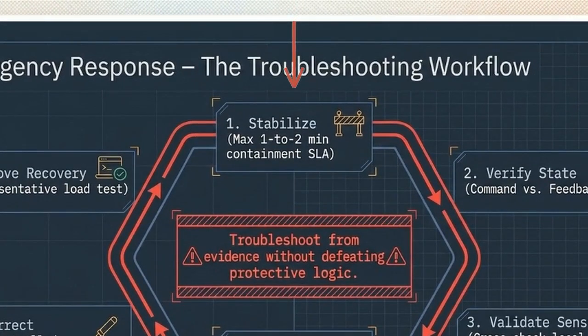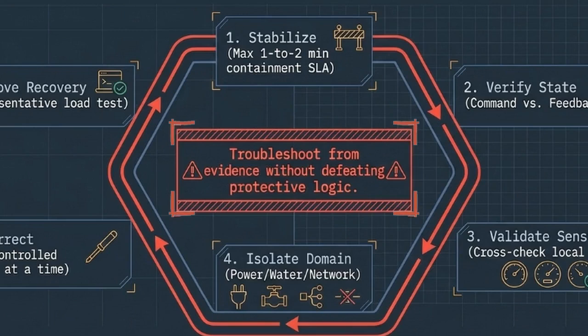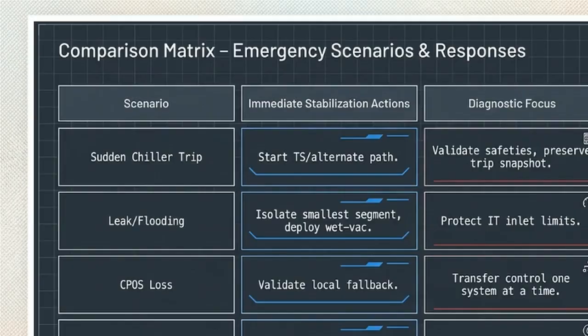By Step 3, operators must cross-check local physical gauges against the control system to validate sensing and rule out false signals. The center warning box highlights the absolute rule of emergency troubleshooting: troubleshoot from evidence. Never defeat local protective safety logic to force an equipment restart. This matrix dictates exact responses to edge case scenarios.